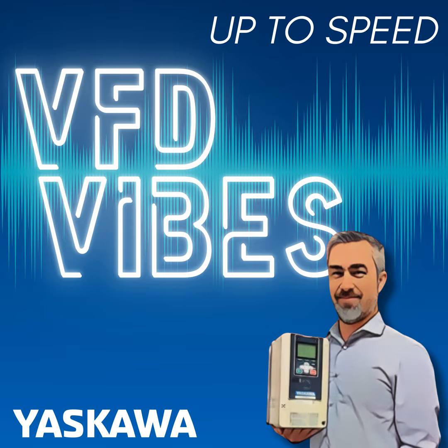If you're interested in how to make things turn, or manufacturing technology in general, then this is the place for you. I'm your host, Greg Weichman, and today we're diving into a foundational, but often misunderstood, aspect of VFD applications, power system configurations. Now, what we most commonly see is a neutral grounded, Y-connected, three-phase system. But that's not the only way that three-phase systems can be configured. Today we're going to dive into what the others are and what implications they might have to your VFD installation or application.